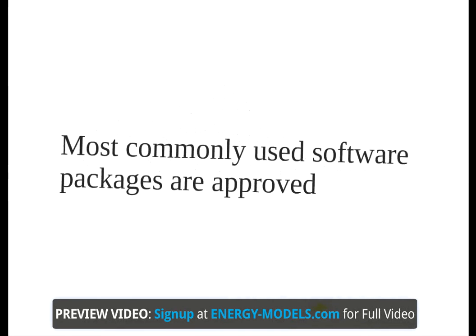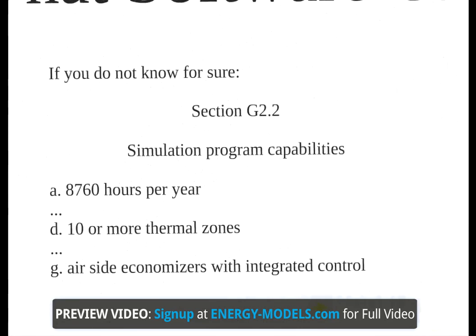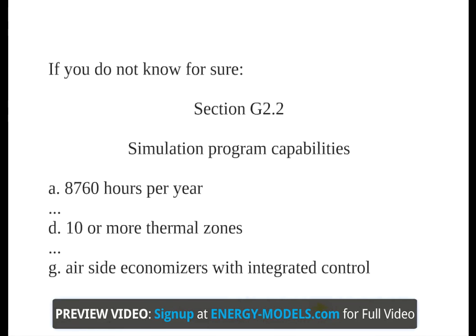Keep in mind that most big-name software packages are LEED approved, but if you do not know, consult Standard 90.1, Appendix G, Section 2.2. It lists required program capabilities such as modeling 8,760 hours per year, 10 thermal zones or more, and also more specific requirements like the ability to model an economizer with integrated control.